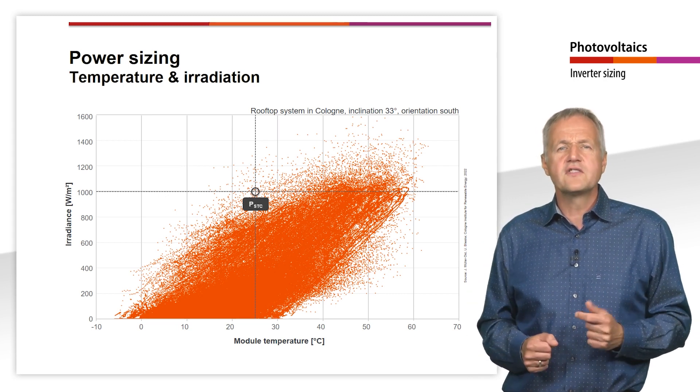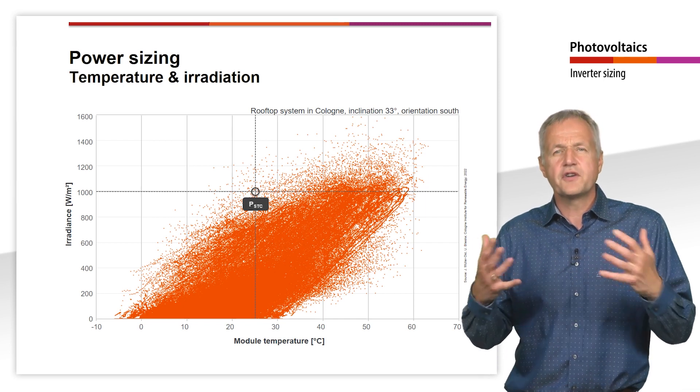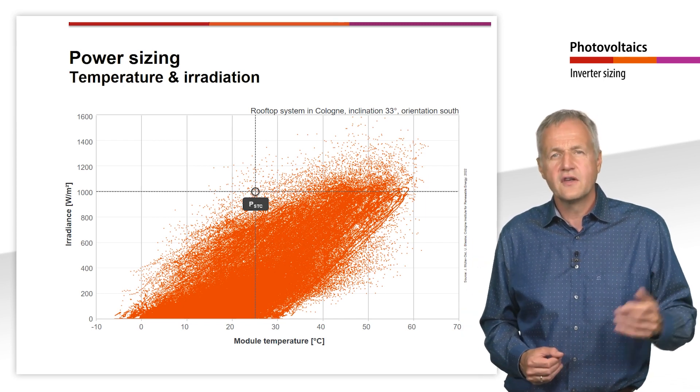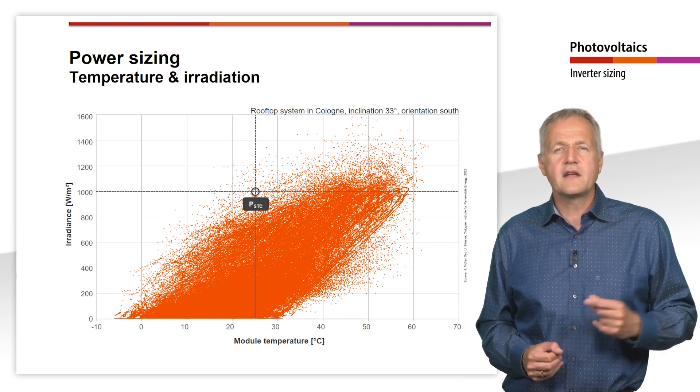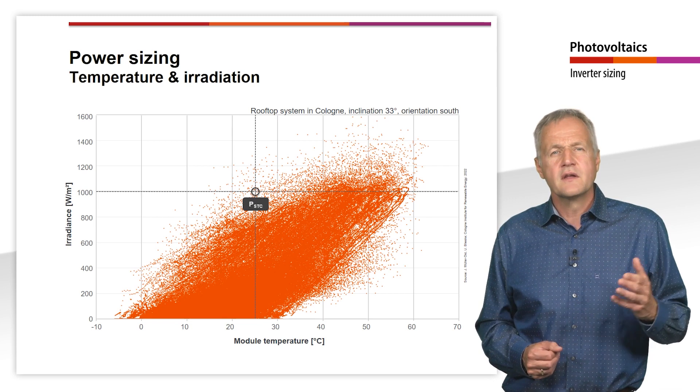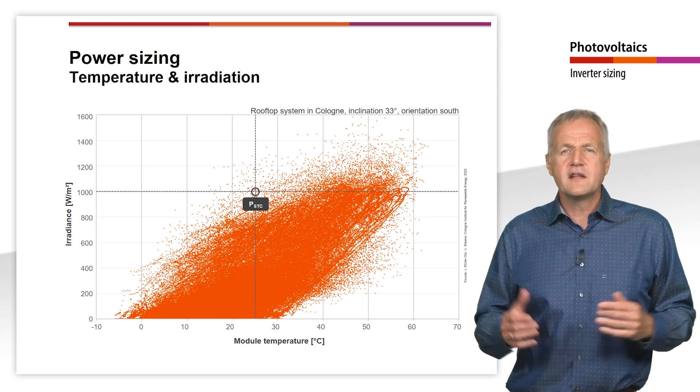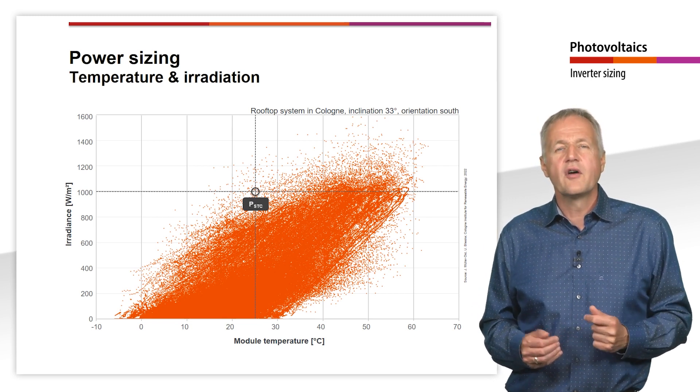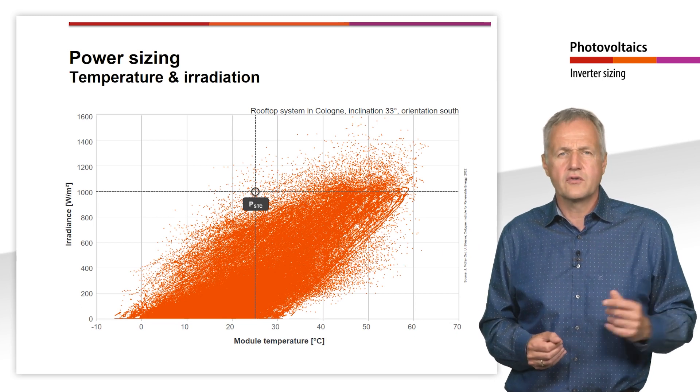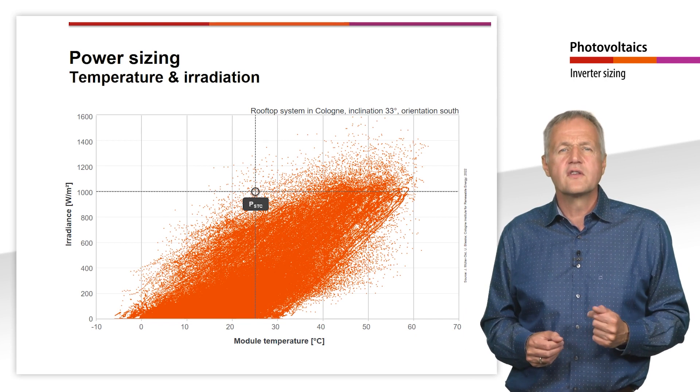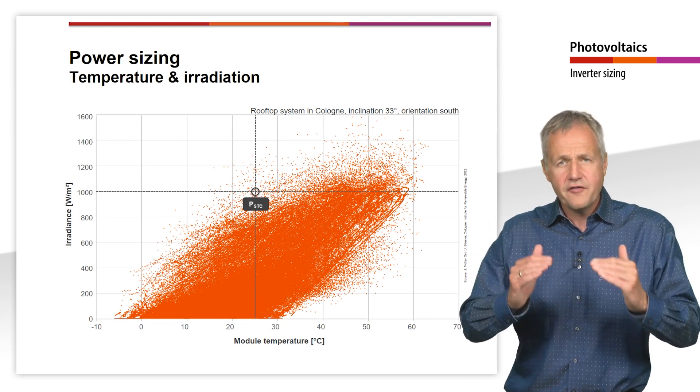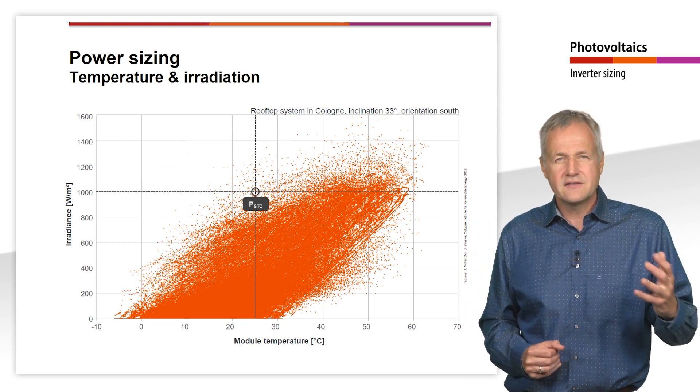Since the solar modules heat up by 20 to 45 degrees Celsius at such high irradiance depending on the installation situation. This can be seen clearly in the diagram shown here for a rooftop installation in Cologne. Due to the heating of the solar modules, their performance drops significantly compared to STC conditions.